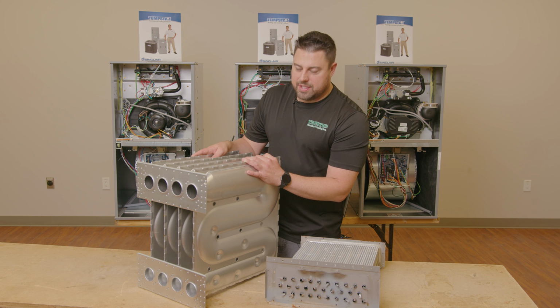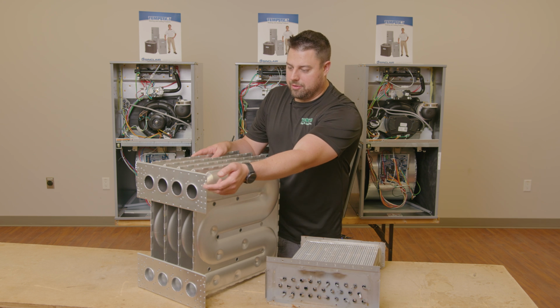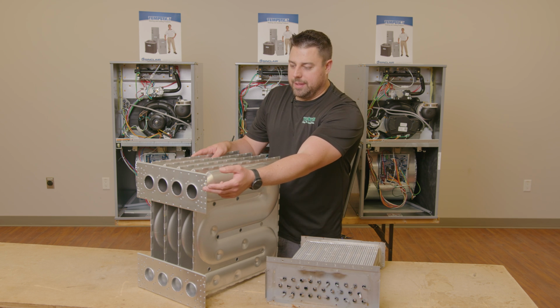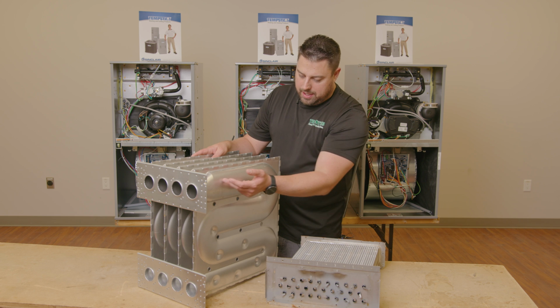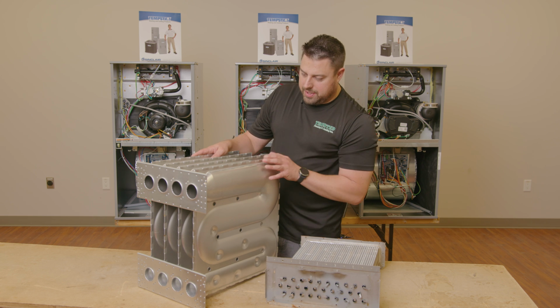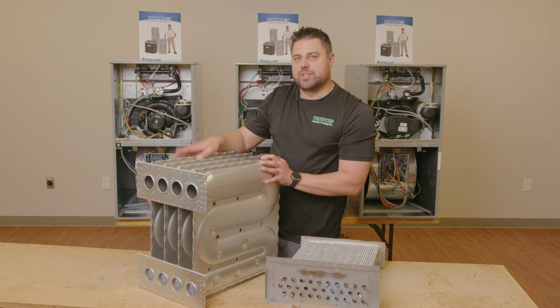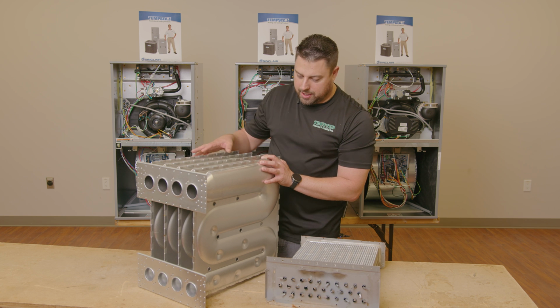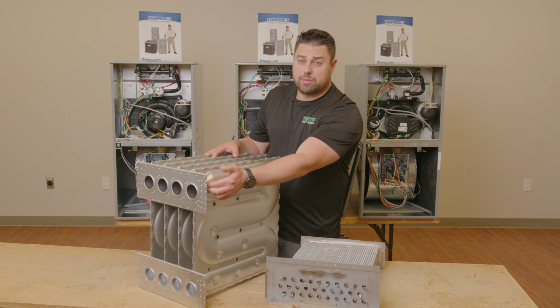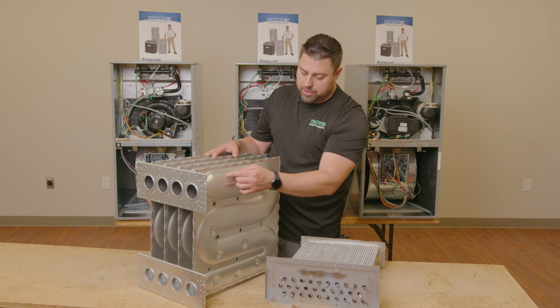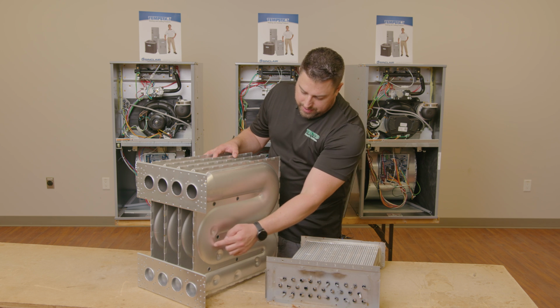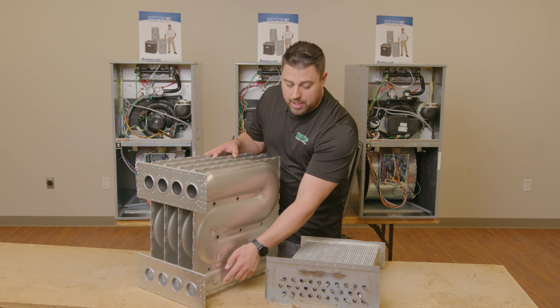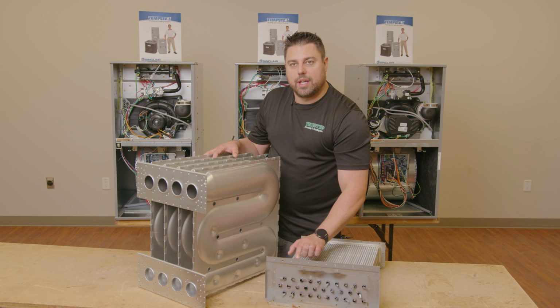Essentially what happens is, as the gas is released through the burner manifold, it gets drawn in through the heat exchanger through these different sections, called cells. These are the 4 different cells on this particular heat exchanger. The inducer motor induces a draft, which pulls the flame all the way through the primary heat exchanger, and it also goes through the secondary heat exchanger.